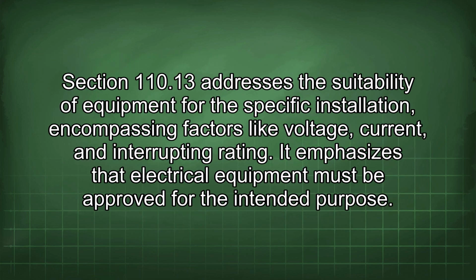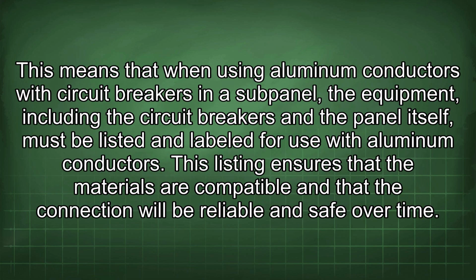Section 110.13 addresses the suitability of equipment for the specific installation, encompassing factors like voltage, current, and interrupting rating. It emphasizes that electrical equipment must be approved for the intended purpose. This means that when using aluminum conductors with circuit breakers in a subpanel, the equipment, including the circuit breakers and the panel itself, must be listed and labeled for use with aluminum conductors. This listing ensures that the materials are compatible and that the connection will be reliable and safe over time.